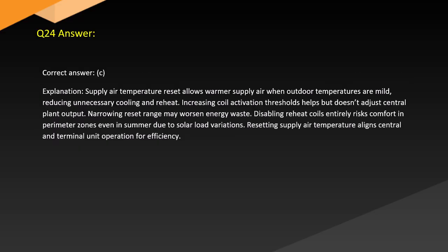Answer. Correct answer: C. Explanation. Supply air temperature reset allows warmer supply air when outdoor temperatures are mild, reducing unnecessary cooling and reheat. Increasing coil activation thresholds helps but doesn't adjust central plant output. Narrowing the reset range may worsen energy waste. Disabling reheat coils entirely risks comfort in perimeter zones even in summer due to solar load variations. Resetting supply air temperature aligns central and terminal unit operation for efficiency.